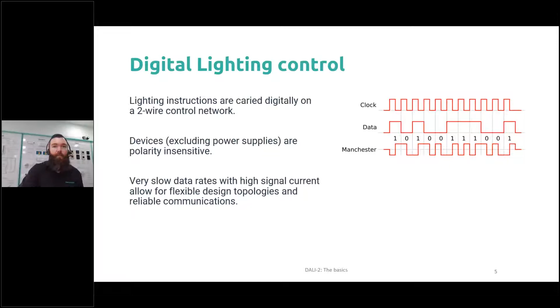So in your DALI networks, you can have a 5-core cable, active, neutral, earth, and your DALI signal within that same cable, without worry of noise or induced voltages. We talked about how we can address: there are 3 levels of addressing depending on how you're looking to control those lights. The standard allows individual lights to be communicated to, but if you've got a group of lights you're interested in, most typically a particular room or section of a room, you can assign them to a group and send commands just to that group.